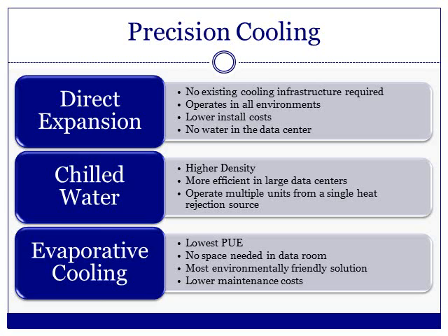Evaporative cooling is also the most environmentally friendly solution. Many solutions rely on outside air to provide sufficient cooling. In some applications, refrigerant-based cooling is used to supplement the evaporative cooling process when the outside air temperatures rise above a certain level. In that scenario, the refrigerant-based supplement only operates on demand. Evaporative cooling's relatively simple design means lower maintenance and repair costs in the future.